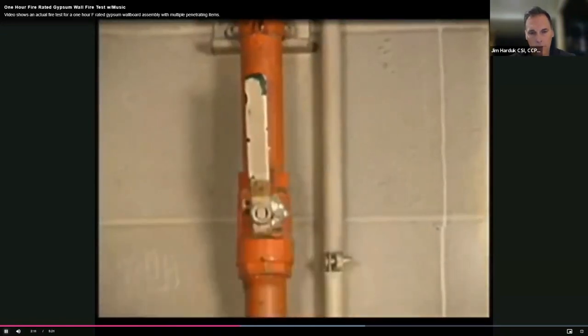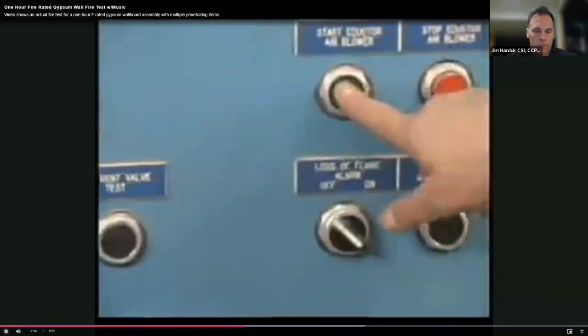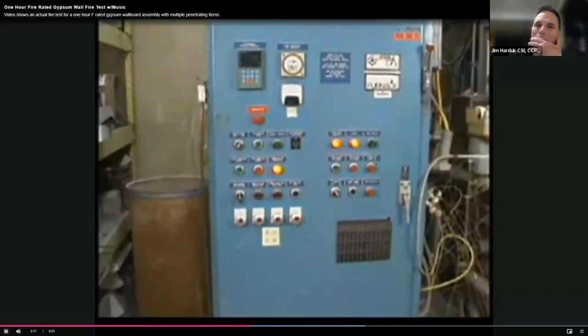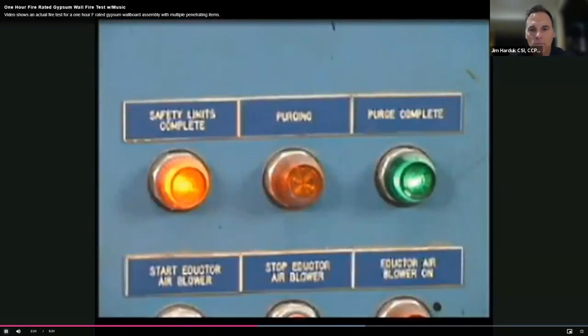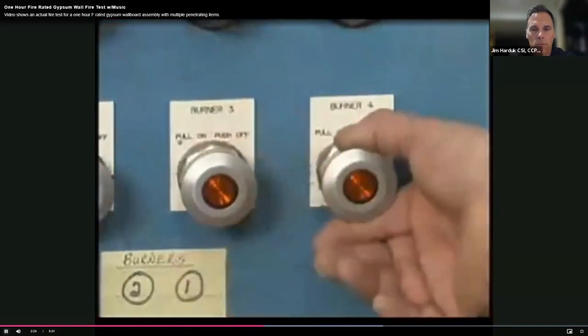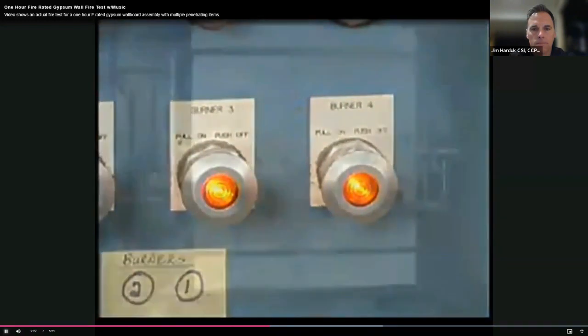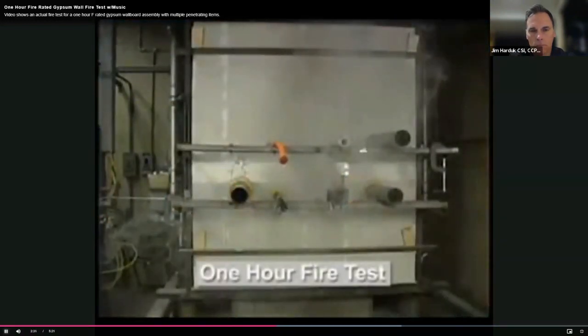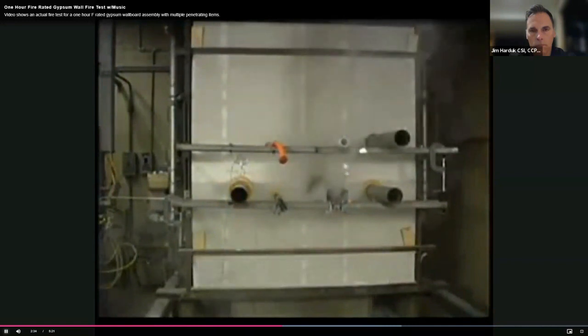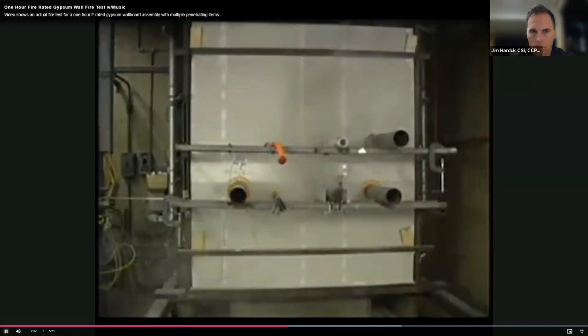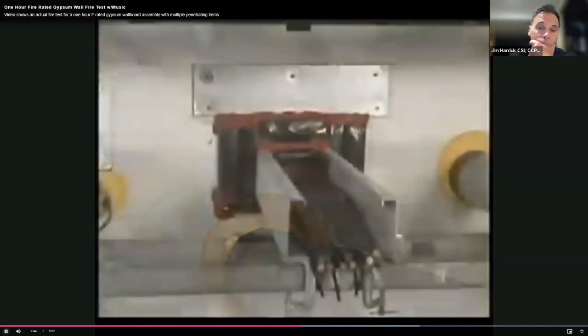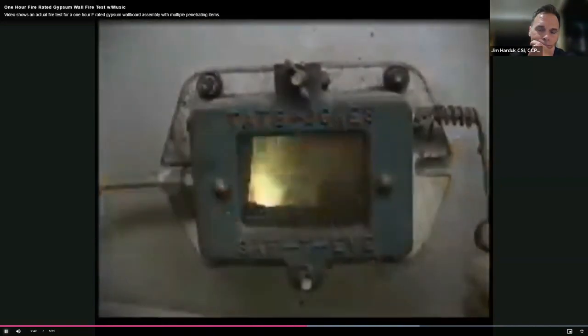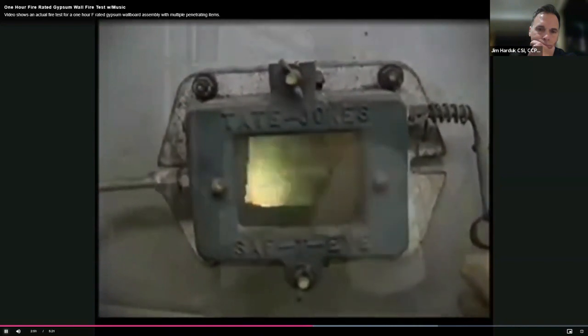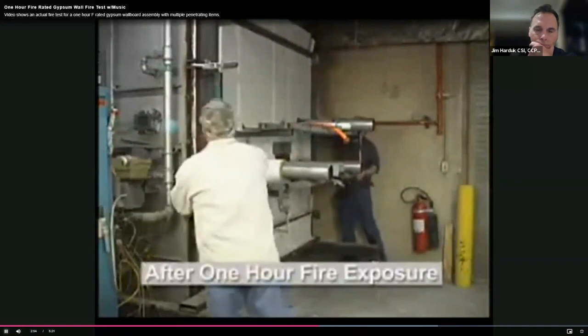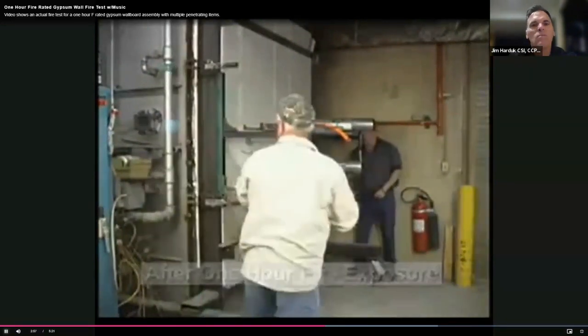The gas valve has been turned on and the furnace has been purged. The furnace has been started. Some smoke is being seen from the penetrating items in the wall. This is a very common situation due to the combustible items which give off toxic gases. The plastic pipes, pipe insulation, and the jacketed cables are giving off smoke. You can see the severity of the fire in the furnace viewport. The temperatures at the end of a 1 hour fire test are at 1700 degrees Fahrenheit.